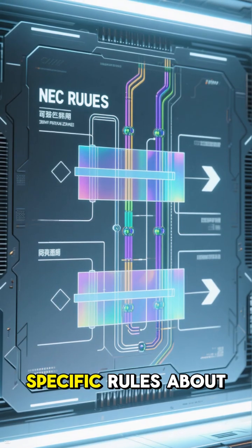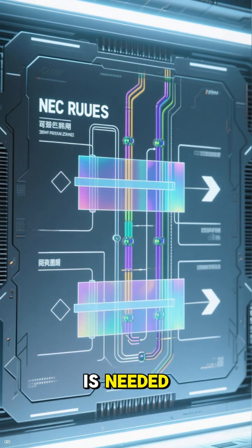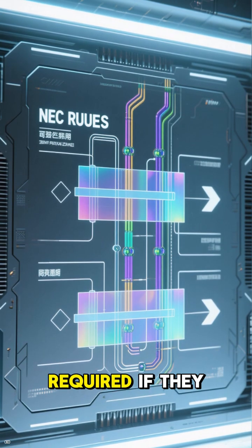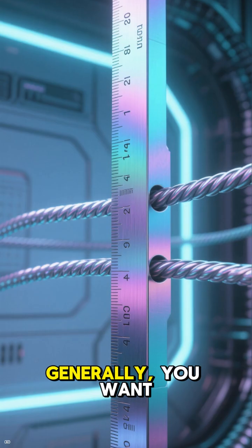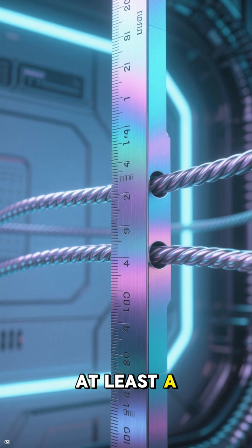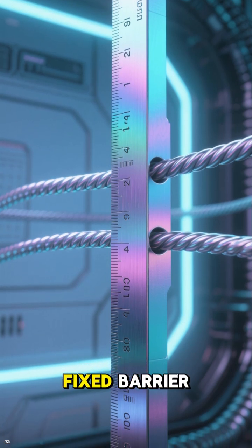The NEC has specific rules about how much separation is needed, or what kind of barriers are required if they have to be in the same enclosure. Generally, you want to maintain at least a quarter-inch of separation, or use a fixed barrier.